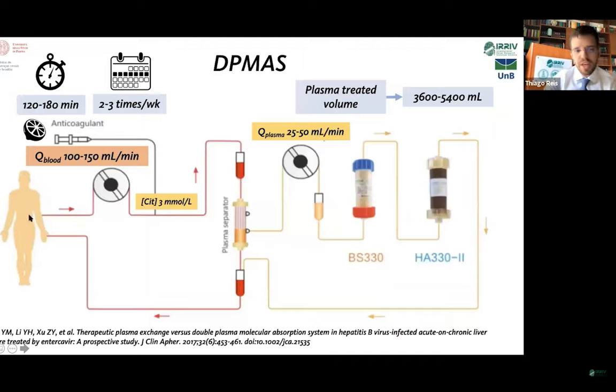The extracorporeal circuit for DPMAS is a therapy that takes two to three hours, two to three times a week. The blood flow in the circuit is 100 to 150 mls per minute. The blood passes through the pump, gets citrate, and then goes through a plasma filter that directs 30% of the plasma to a parallel limb of the circuit. Then there is another pump for the plasma, passing through BS-330 and then HA-330, finally returning through the deaeration chamber back to the patient.